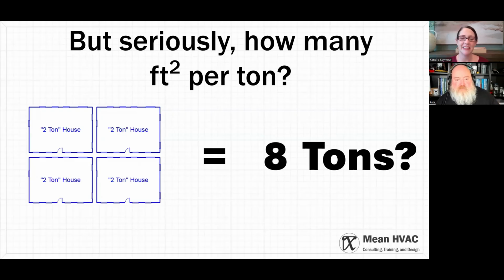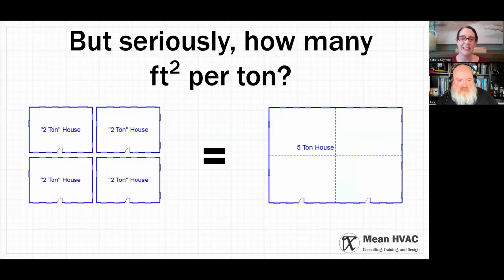Well, if you smushed them all together, you don't need 8 tons, you need about 5. That's because these outside walls that had windows and heat coming through them are now inside walls with no heat coming through them. Same square footage, 8 tons goes to 5 tons. Square footage rules cannot work, right? Not that they don't, they cannot work. It's physically impossible. Heat does not come through interior walls, it comes from the outside.